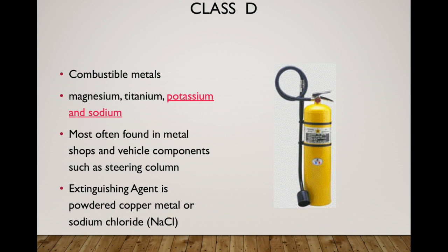This agent doesn't necessarily dispel like out of a dry chemical extinguisher or even a CO2 extinguisher. The agent sort of pours out of the nozzle. So that nozzle wand actually needs to be brought right over the agent, and you just work it slowly back and forth to completely cover the agent, which as it reacts with the metal will form a crust over the top of it.